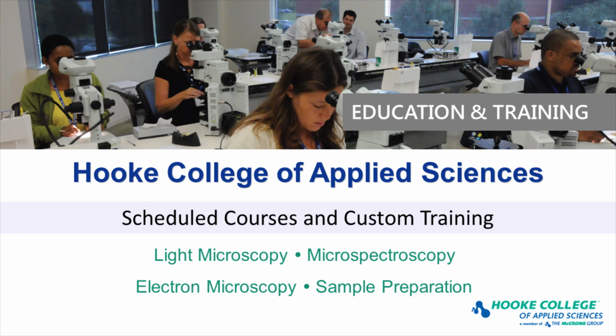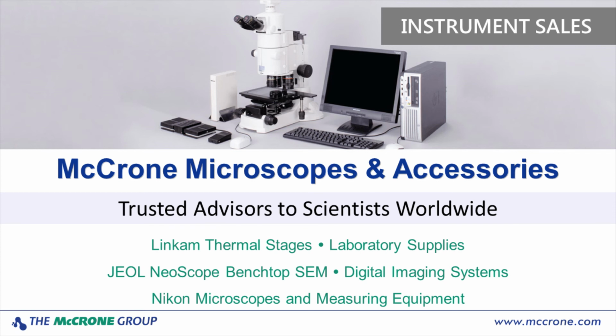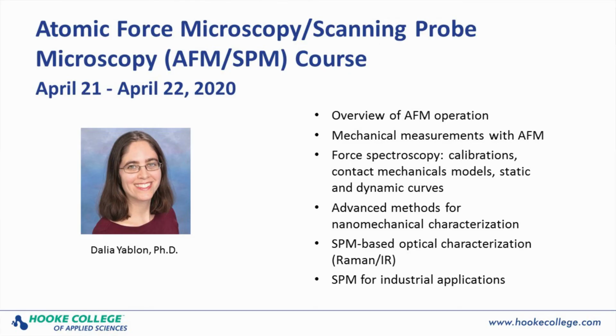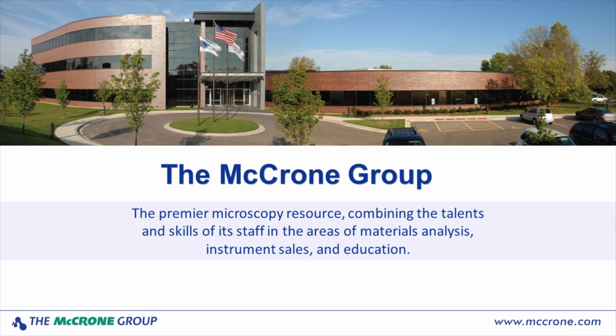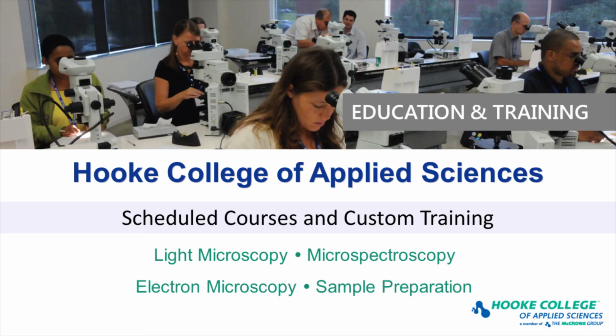You can do them either in the traditional way, which is a thermal method, or you can now buy cantilevers that are pre-calibrated by laser Doppler vibrometry, and then the optical sensitivity calibration is done the way it's always been done, which is a force curve on a stiff sample like sapphire. But the technique doesn't require any tip shape calibrations, which is always the concern for these nanomechanical measurements. In addition to the spring constant and sensitivity measurement, it does have another calibration required, related to the electronics and the phase of the instrument, which you also calibrate on a sapphire sample. So that is a step that has to be done, but the classic tip shape and tip radius calibrations are not required for AFM nano DMA.